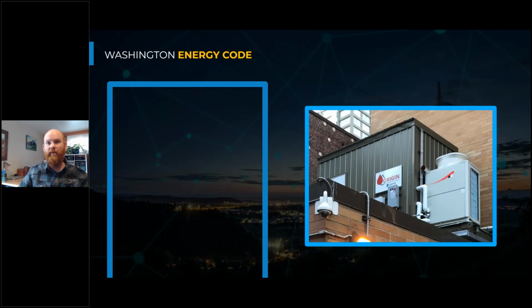Here's one of our heat pump water heating systems installed in downtown Seattle. This is for the Bayview Tower, which is an existing building that was retrofitted with the heat pump water heating system. And this is a CO2 heat pump water heating system that's all packaged together. And if anyone was at AHR a few weeks ago in the Las Vegas area, I wasn't able to attend, but one of my coworkers went, and they had this unit on display, or a system very similar to this. But we can see that these systems can be dropped in place in many locations. We can retrofit buildings even if there's not much room in the existing plumbing or mechanical room for this equipment.